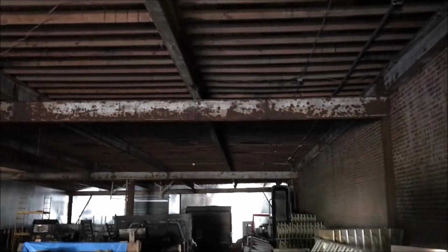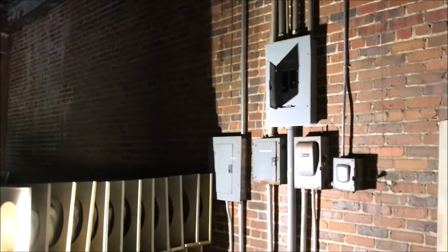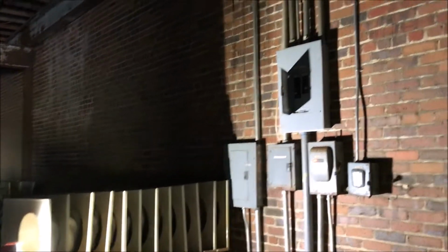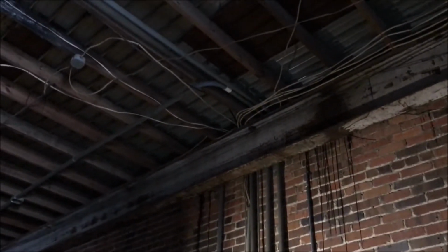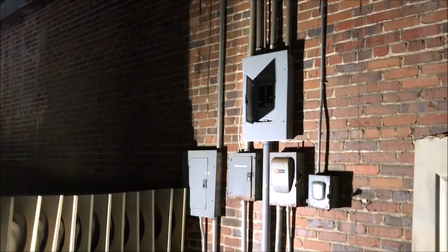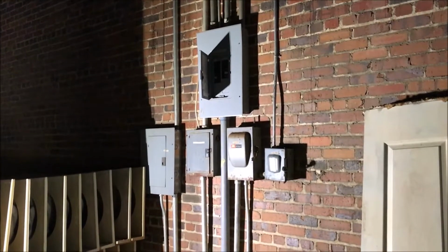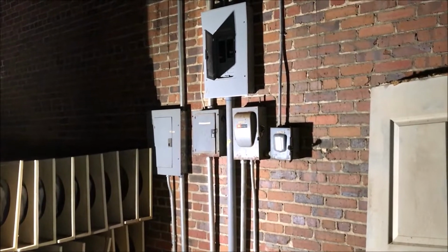Lots of old light fixtures. Just stuff everywhere, and it goes all down through there, right? So when we found it, we've cut it out because we don't want to reuse the old stuff. Now you may say that's crazy, but I don't like having exposed Romex like that, and you know, it's just, I don't like that. I like stuff being in conduit or in the wall or in metal clad, you know, something. So we're not going to reuse this, but it's high time that we got some power on this building.